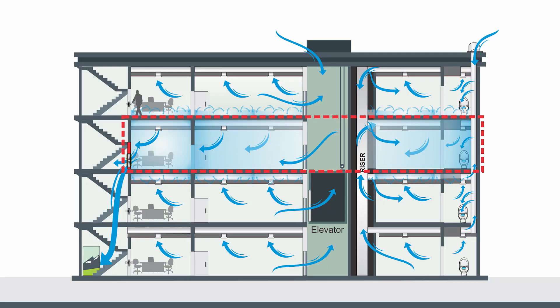By the same token, we try to eliminate any leakage that is not going through the designed air barrier. The worst case a tester can do is just pick one room and run what we call an unguarded simple compartment test. Usually the only time we would do that type of test is during the extremely early stage of a project where a small section of the building is complete — the purpose is just to show the trades and site staff where the sources of leakage could be. It's more qualitative than quantitative — you pressurize, fill it with smoke, and you can see it coming out of the facade.